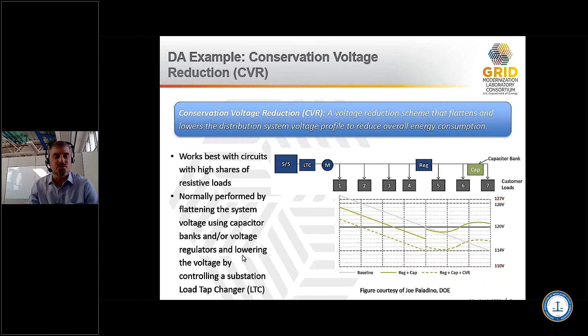When you have a bunch of actual equipment out on the line, voltage regulators, cap banks, maybe even PV inverters and distributed energy resources that can be controlled via the utility, and you have a complex distribution management system on top seeing all that information coming back and providing set points, you might actually be able to do a really good job of conservation voltage reduction. That's one of the ideas.